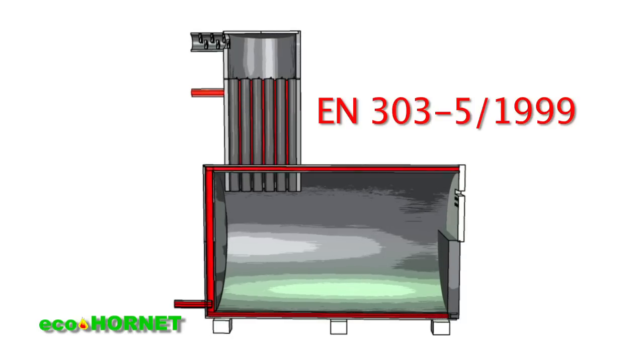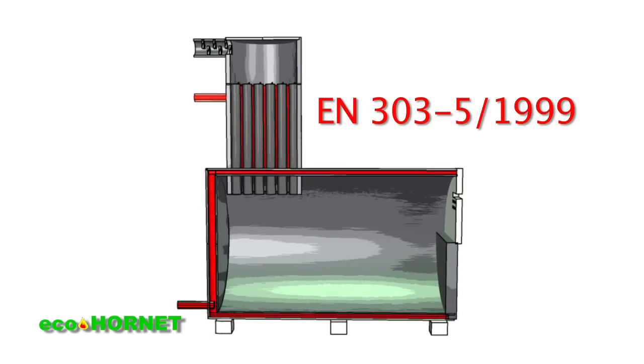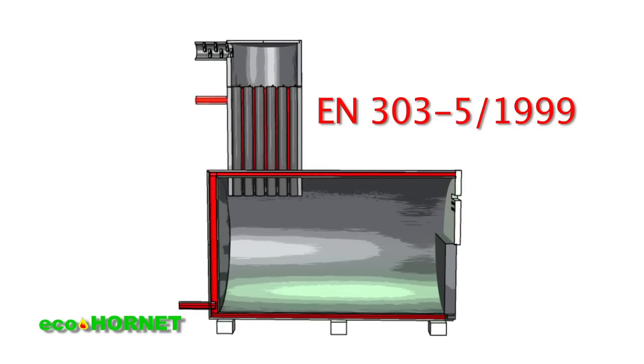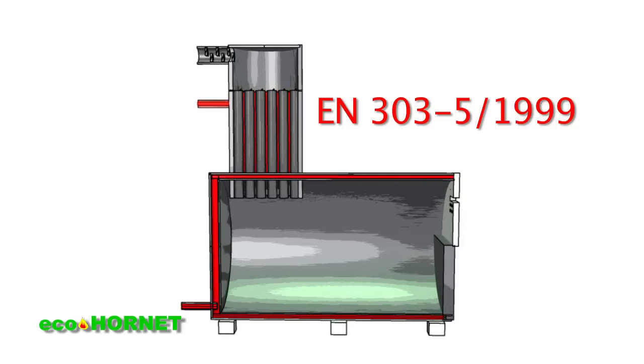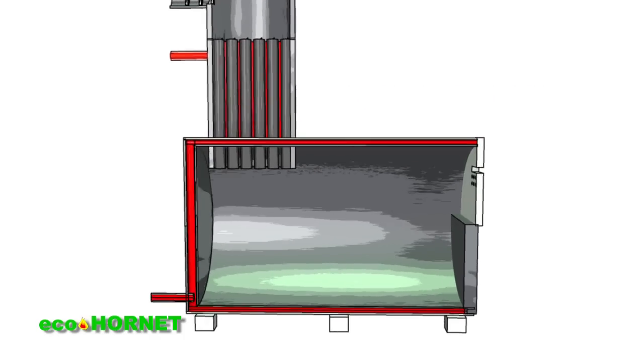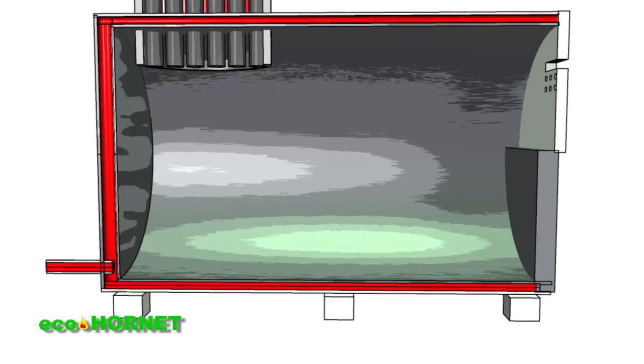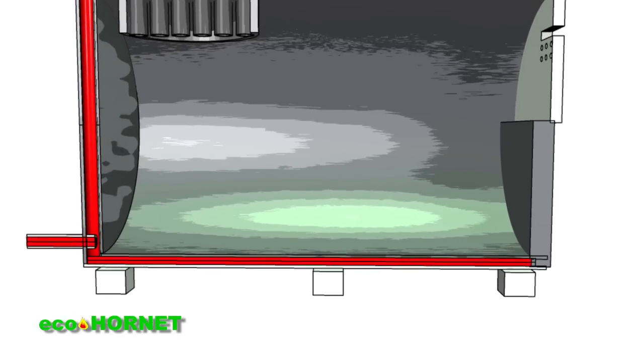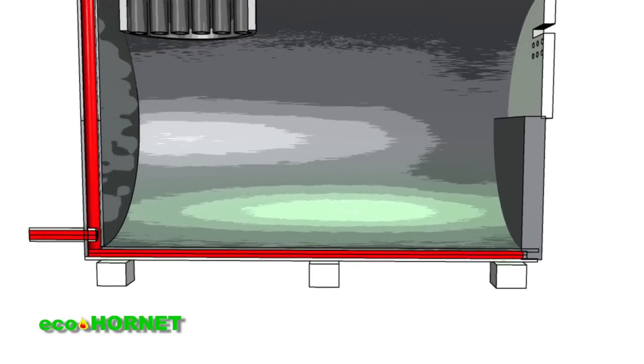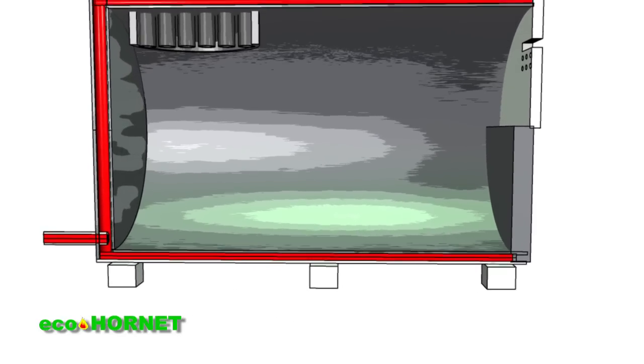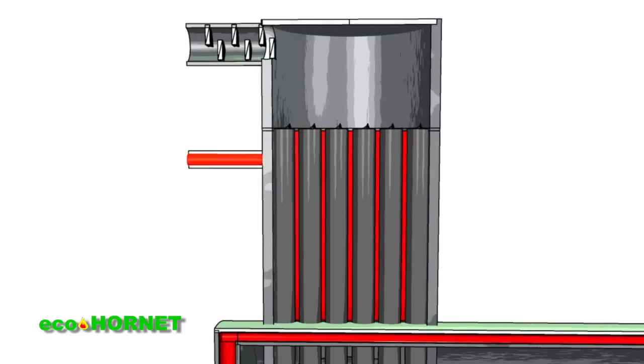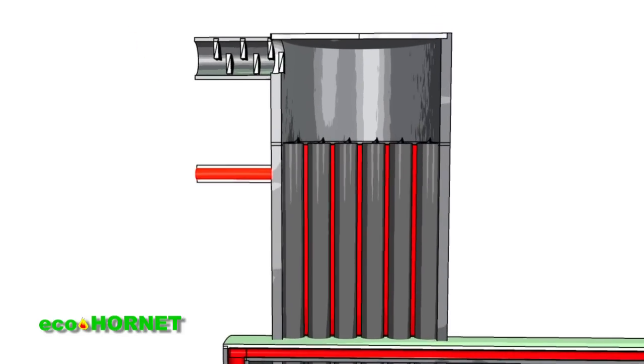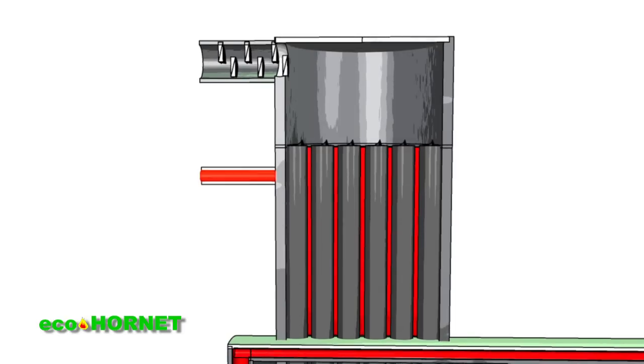The heat exchanger is made of steel according to EN 303-5-1999 and has two distinct areas: a horizontal cylinder with double walls which circulates the heating agent heated by radiation from the flame, and a vertical cylinder area in association with a horizontal area which houses a number of pipes for burnt gas, called the convection area.